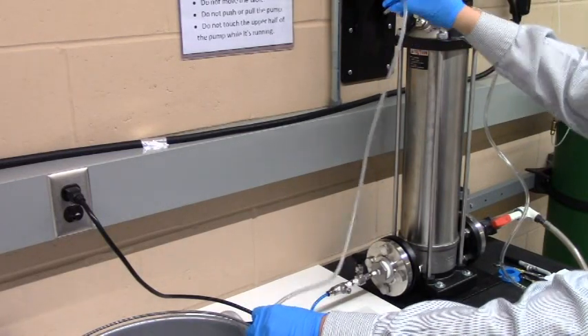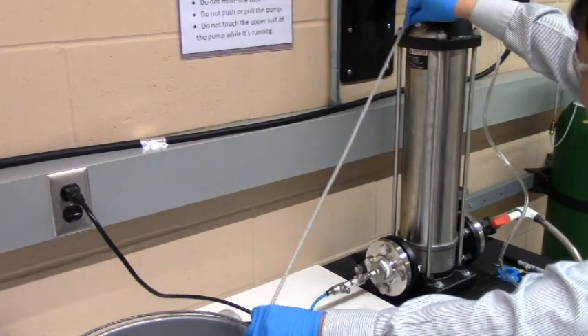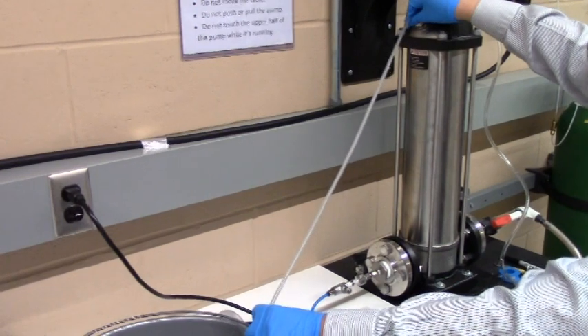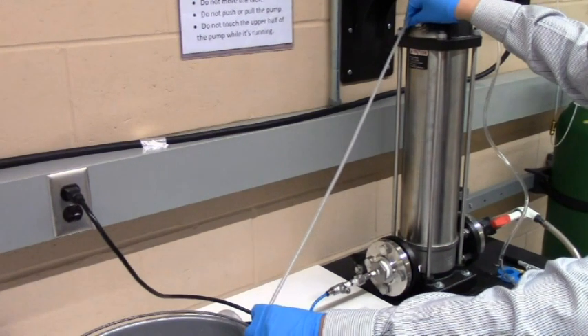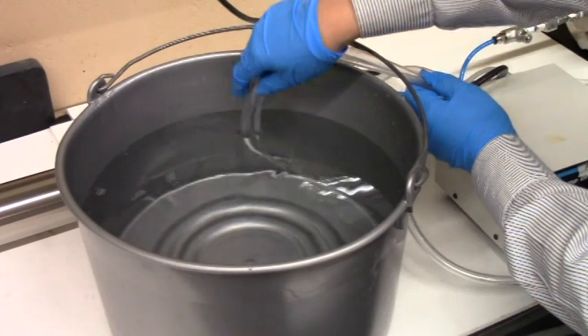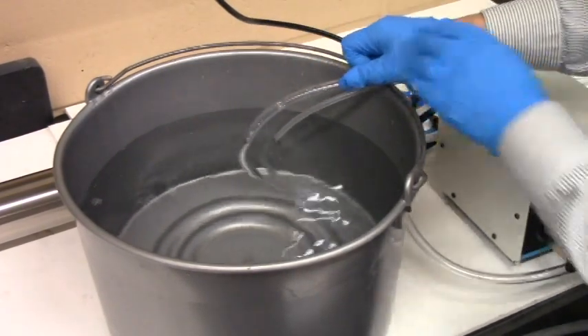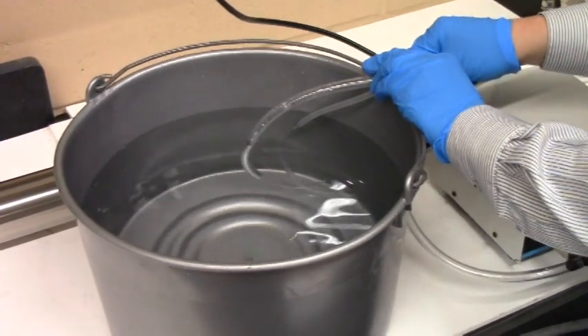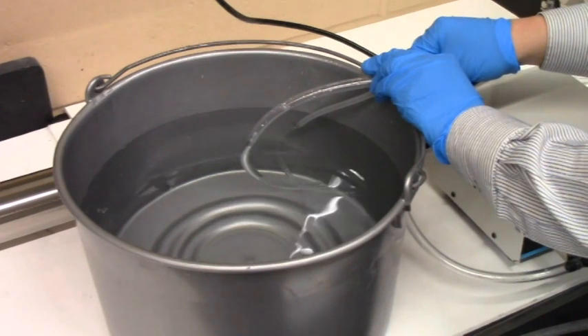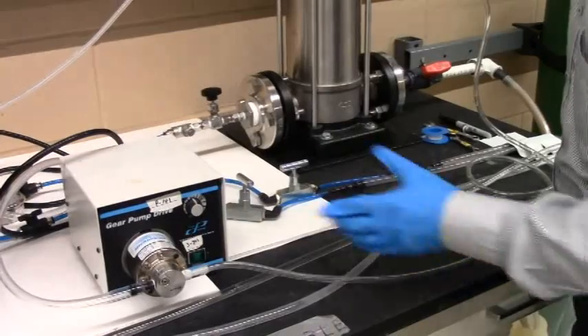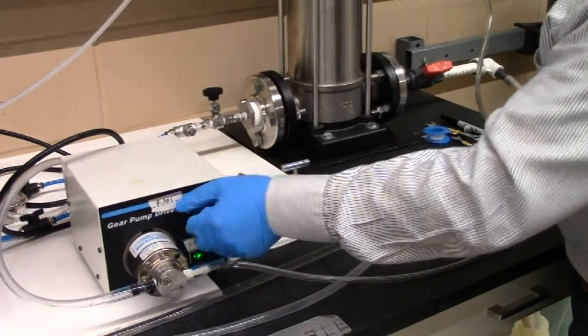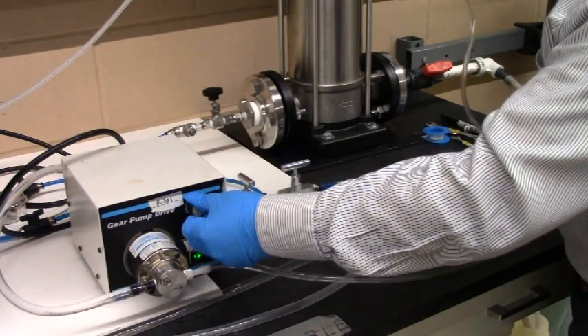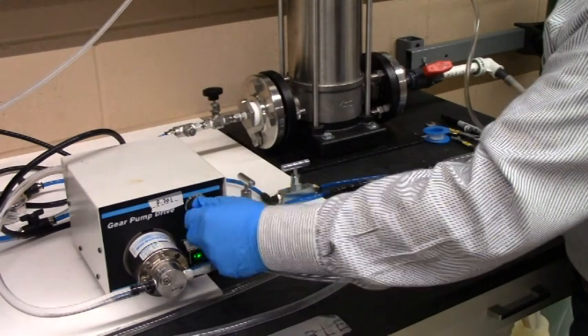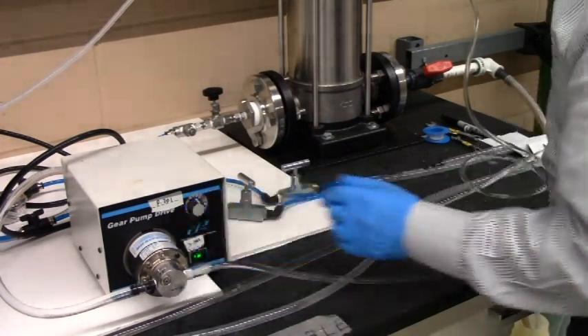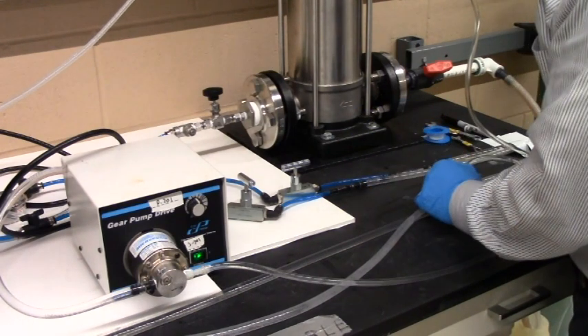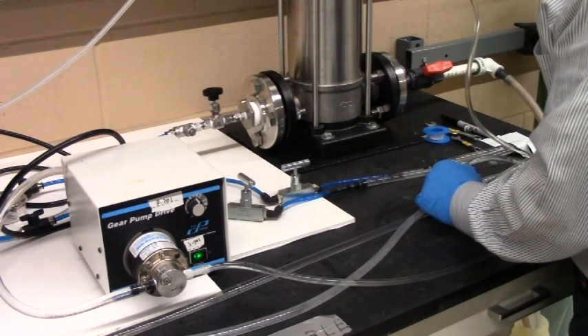While one end of the small plastic tube is in the bucket of water, you need to hold the other end and press it into the prime outlet. Make sure to hold one end of the small plastic tube and the suction tube of the gear pump so that they are submerged in the water. Flip the switch of the gear pump, dial up the black knob past halfway, and wait until water goes up to the prime inlet. Then close the suction valve and discharge valve of the centrifugal pump.